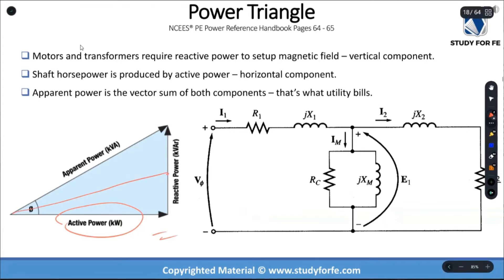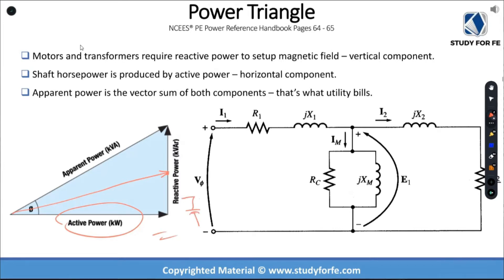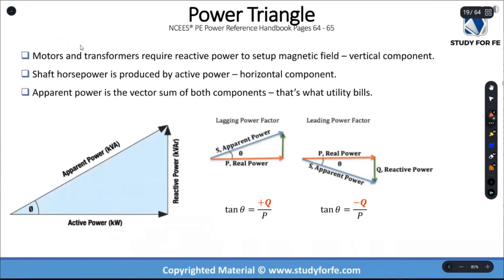To be more specific, it changes the reactive power supplied by the utility or the source. When you add a capacitor in parallel, this capacitor is a source of reactive power and it basically locally provides reactive power to your load, which results in a decreased draw of reactive power from the utility. The reactive demand is still there from your inductive load, but it is being locally provided.